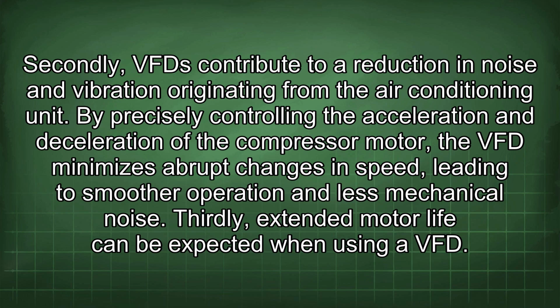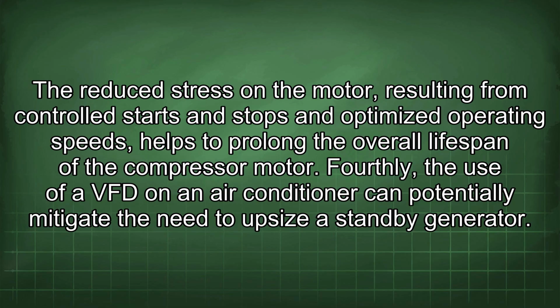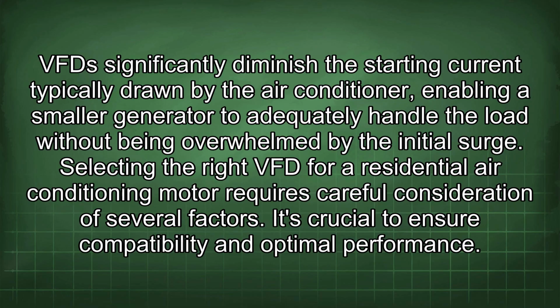Thirdly, extended motor life can be expected when using a VFD. The reduced stress on the motor, resulting from controlled starts and stops and optimized operating speeds, helps to prolong the overall lifespan of the compressor motor. Fourthly, the use of a VFD on an air conditioner can potentially mitigate the need to upsize a standby generator. VFDs significantly diminish the starting current typically drawn by the air conditioner, enabling a smaller generator to adequately handle the load without being overwhelmed by the initial surge.